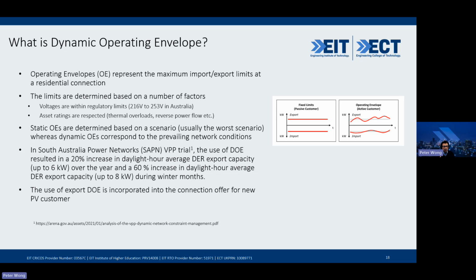It's based on voltage, to make sure the voltage stays within the regulation limits. In Australia, the low voltage is between 216 volt and 253 volt. There are also asset ratings, such as thermal limits and reverse power. For example, some distribution transformers might have limited reverse power capability, and there is also thermal overload, which the generation could cause. So you have these limits, and they define how much each customer can actually import or export from the electricity network.